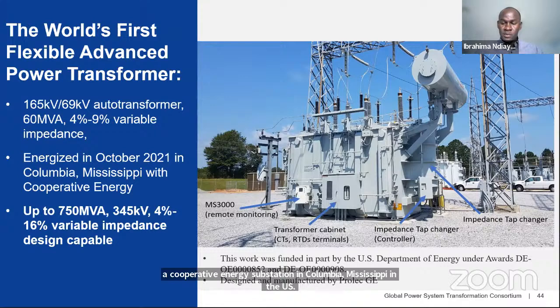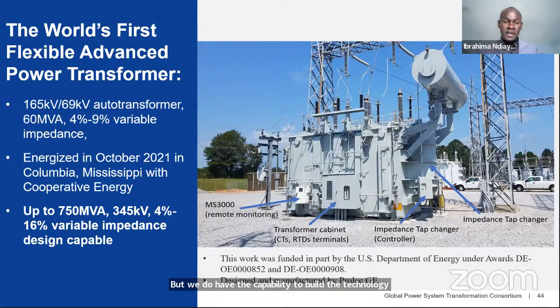We do have the capability to build the technology up to 750 MVA, three-phase, up to 345 kV, with the impedance range shown, and obviously we can go higher than this rating. We think this will be most optimal because, taking the US grid, 230 kV has been the backbone, which is where most interconnection happens. Now, through electrification and decarbonization, the backbone is growing toward 345 kV, so that's probably where most interconnection will happen within the next two decades as we build out the next generation of grid.